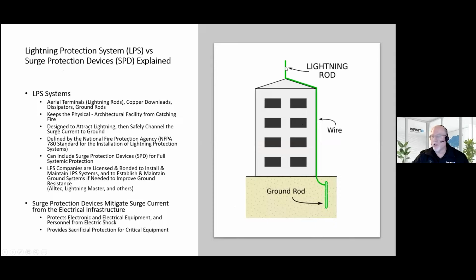So the lightning rod is attracting lightning. It wants to be hit, and then it safely channels it away. You might see a lightning rod about every 10 or 20 feet around the perimeter of a building or a fuel tank or something like that. So LPSs are not surge protectors. Surge protection devices protect the electrical infrastructure, all the wiring within the building, to keep that from catching on fire and so on. But they can be obviously used together. And in some cases, you might want to do that.